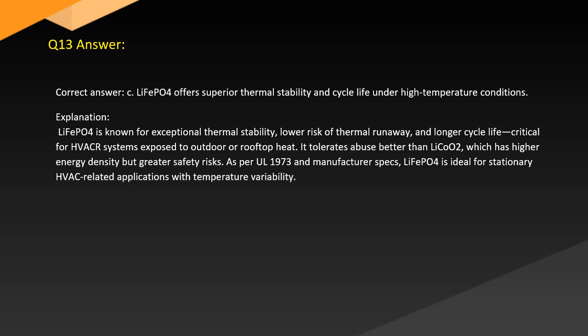Answer. Correct answer. C. LiFePO4 offers superior thermal stability and cycle life under high temperature conditions. Explanation. LiFePO4 is known for exceptional thermal stability, low risk of thermal runaway, and longer cycle life. Critical for HVACR systems exposed to outdoor or rooftop heat, it tolerates abuse better than LiCoO2, which has higher energy density but greater safety risks. As UL 1973 and manufacturer data note, LiFePO4 is ideal for stationary HVAC-related applications with temperature variability.